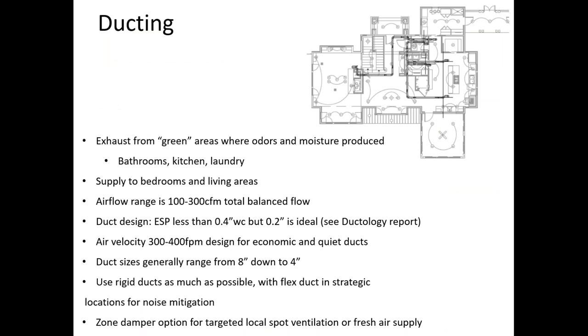For the ducting throughout the house, what we recommend and what most spaces follow is pulling air from the green areas where odors or moisture are produced, like bathrooms, kitchen, and laundry, and then supplying to bedrooms and living spaces. Configuration can change depending on what the homeowners want to accomplish in the house. For general air quality, you may just be connecting the CERV2 to a central air handler, so a central heating or cooling system. The CERV can connect to those fully and just manage the general air quality by siphoning air off of that airstream and injecting fresh air back in when needed.